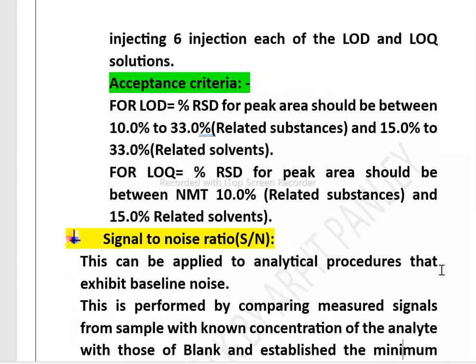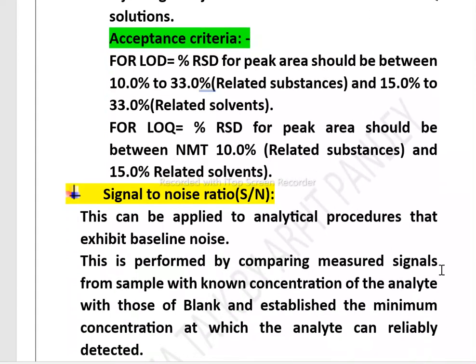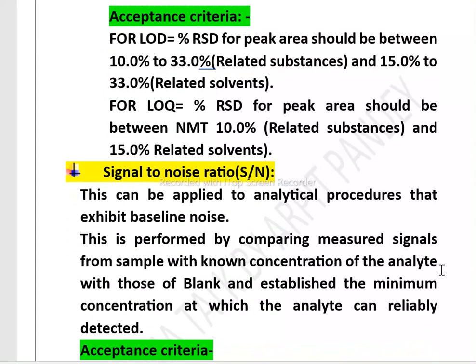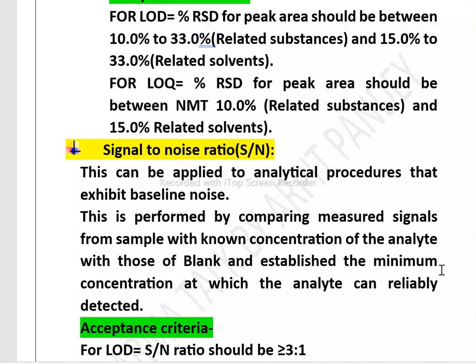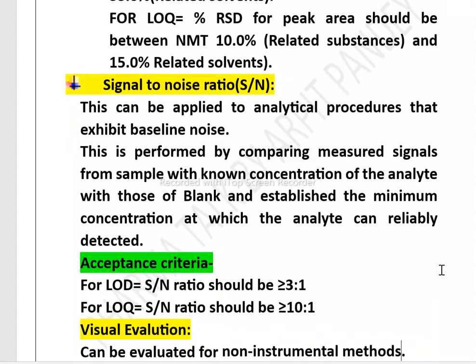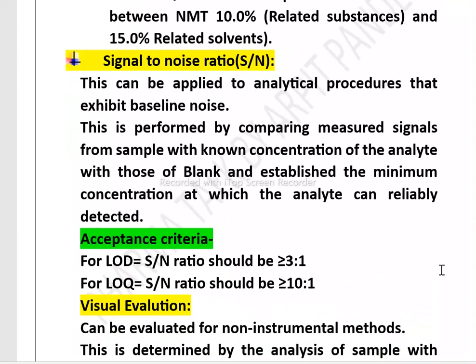If we determine LOD and LOQ using the signal-to-noise ratio method, the procedure is as follows: this can be applied to analytical procedures that exhibit baseline noise. It is performed by comparing the measured signal from a sample with a known concentration of the analyte against those of blank, and establishing the minimum concentration at which the analyte can be reliably detected. The acceptance criteria for LOD: the signal-to-noise ratio should be greater than or equal to 3:1.